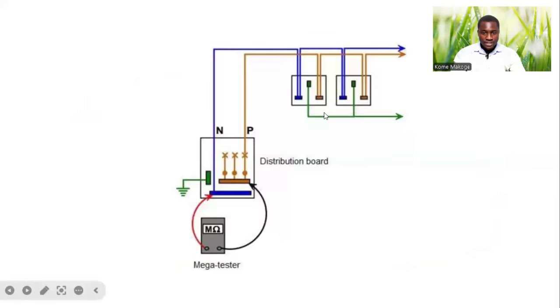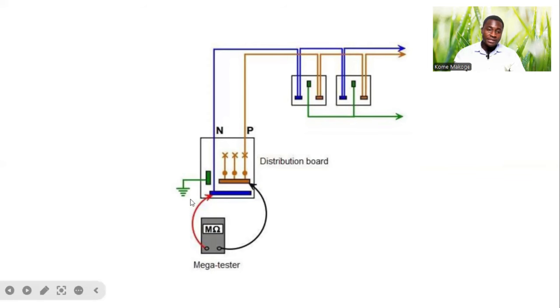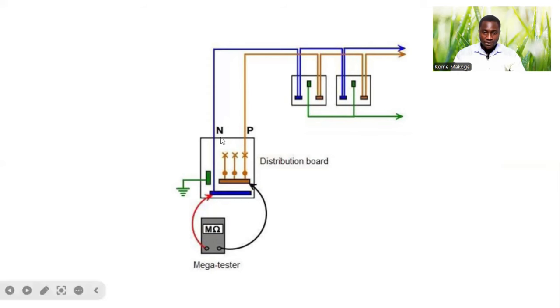We move to this picture where we have two circuit outlets that have been installed and then we have our distribution board. In this case, we will be performing the Insulation Resistance Test using the Mega Tester by testing between the phase and the neutral from the DB side, to ensure that we will not have any interconnection between the phase and the neutral conductor.